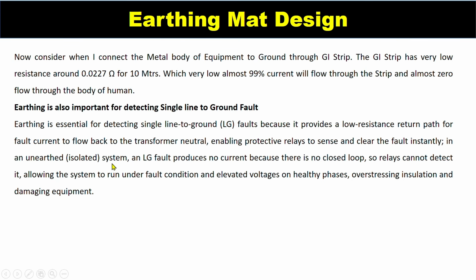In an unearthed isolated system, single line to ground fault currents are not produced because there is no closed loop, so a relay cannot detect it, allowing the system to run under fault conditions and elevating the voltage on the healthy phases, causing overstressing of insulation and damaging the equipment. That means if a single line to ground fault occurs in any unearthed, ungrounded system, the single line to ground fault current will not flow because there is no closed loop, because the system is ungrounded.